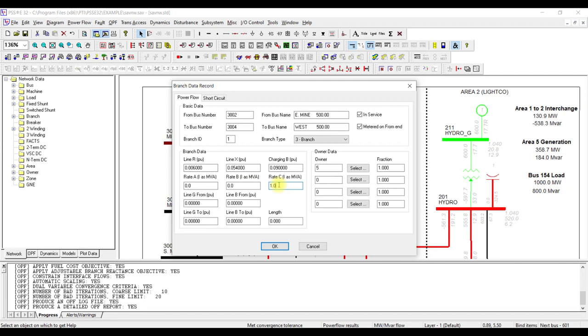Similarly, the length of the line field in PSS/E is just for reference — PSS/E will not convert per-kilometer values into total length by multiplying with this factor; you have to do that manually before entering. If you do not provide a length value, nothing will happen. This field is only for your reference to know how long the line is, and has nothing to do with the calculations.